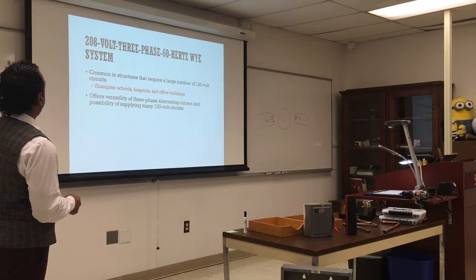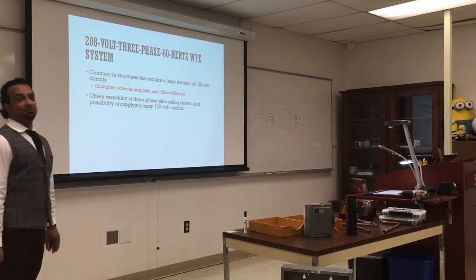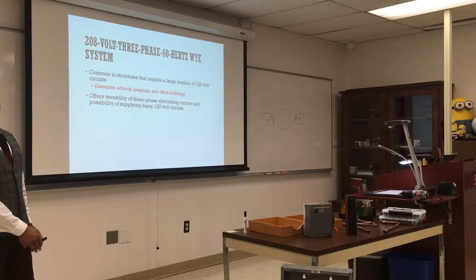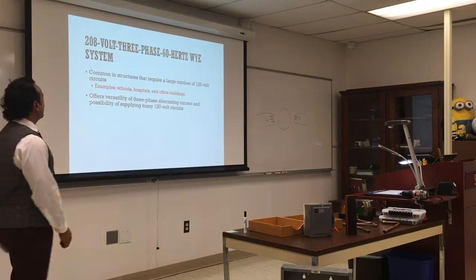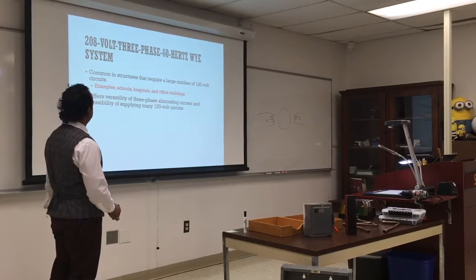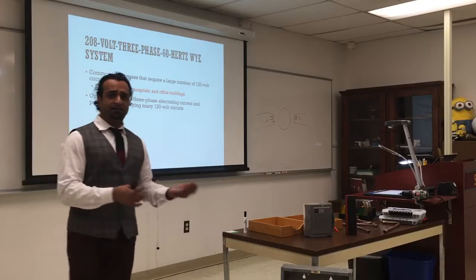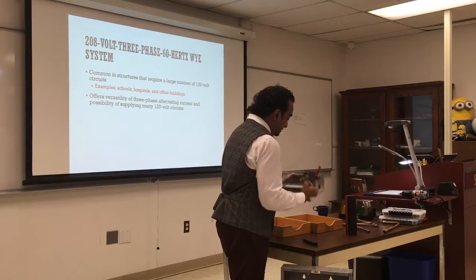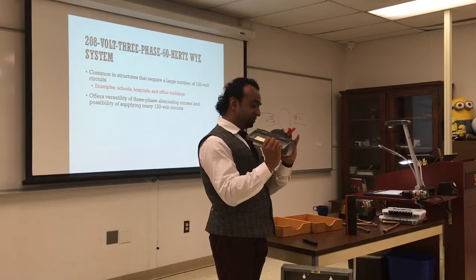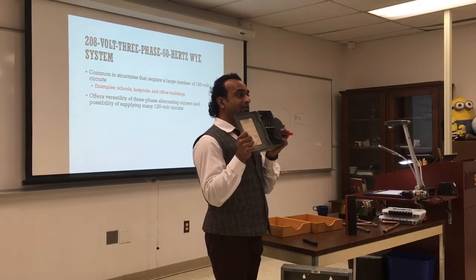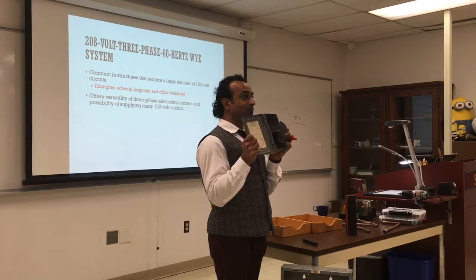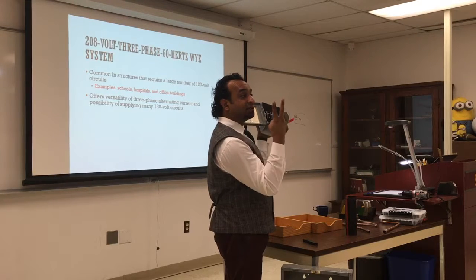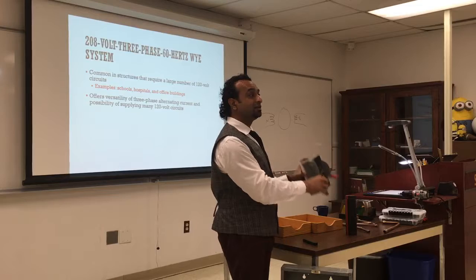208 volts, three-phase, 60 hertz — the Y (wye) system. It looks like a Y. They have it in schools, hospitals, and office buildings. The Y system or the Delta system is to give you more variety — you have three legs. This is a switch box for three-phase. How do I know it's three-phase? There are three hot legs. How do I know there are three hot legs? I have three fuses — that means there are three hot legs, so it's three-phase.